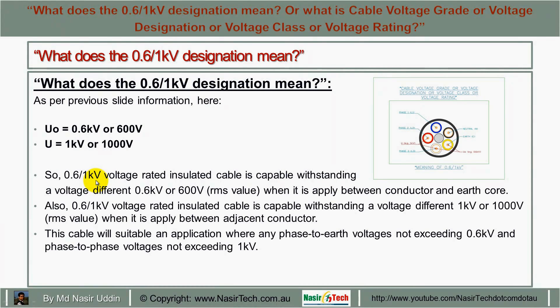So a 0.6/1 kV rated insulated cable is capable of withstanding a voltage difference of 0.6 kV or 600 volt RMS when applied between a conductor and the earth core. Similarly, a 0.6/1 kV rated cable is capable of withstanding a voltage difference of 1 kV or 1000 volt RMS when applied between adjacent conductors.